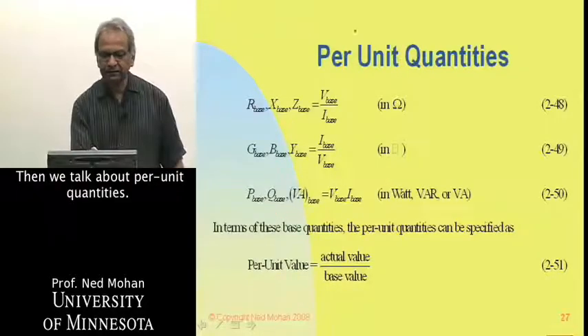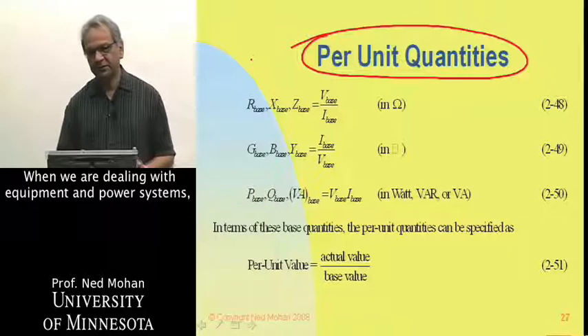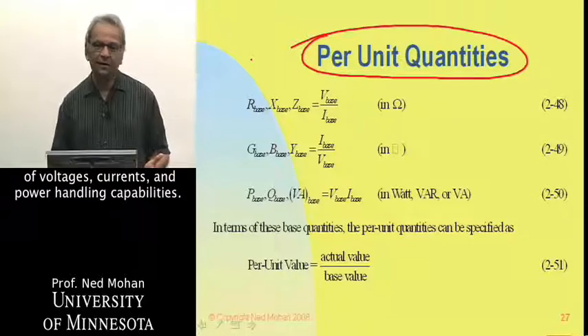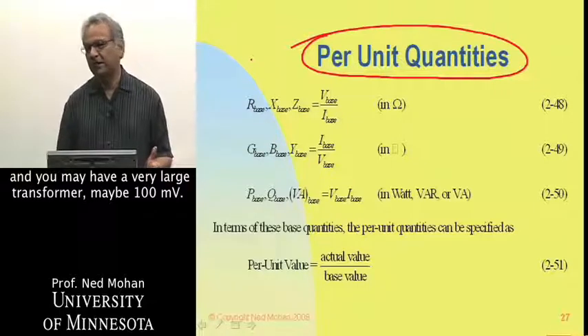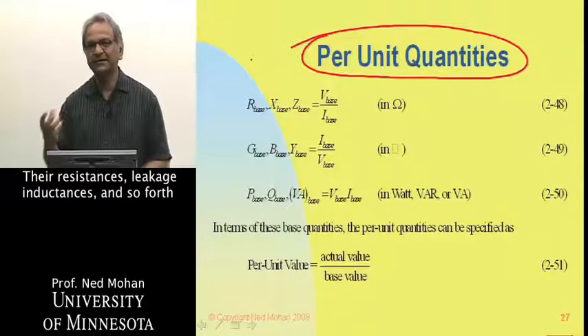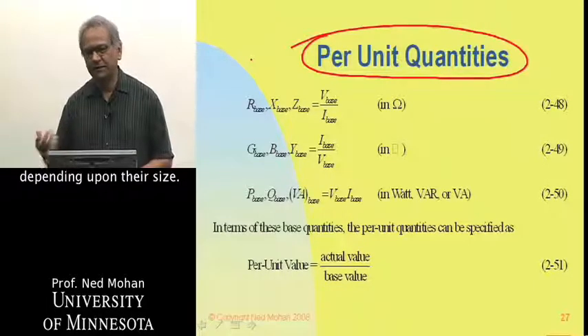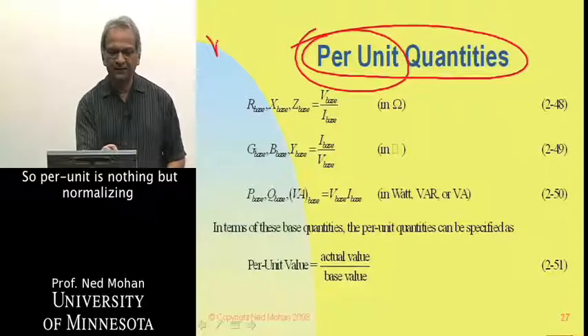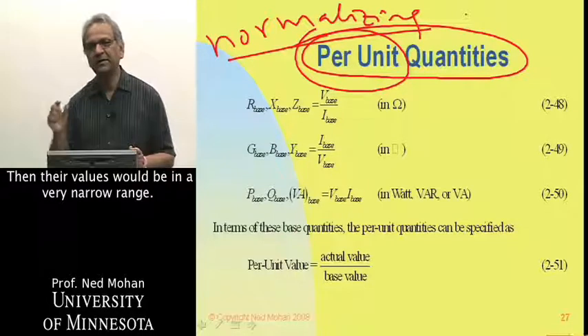Then we talk about per-unit quantities. When dealing with equipment in power systems, equipment could vary in a wide range in terms of voltages, currents, and power handling capabilities — you may have a small transformer of a few kVA or a very large transformer of 100 MVA. Their resistances, leakage inductances, and so forth in ohms would be in a very wide range depending upon their size. But if you normalize them — that is, put them in per unit — their values would be in a very narrow range.